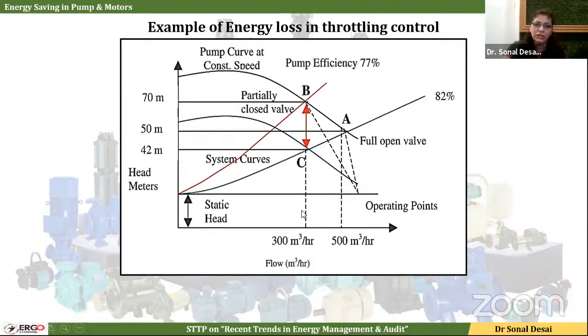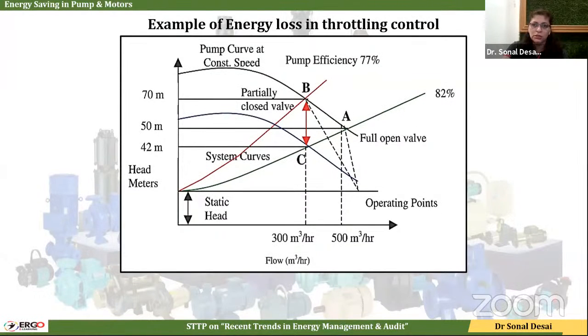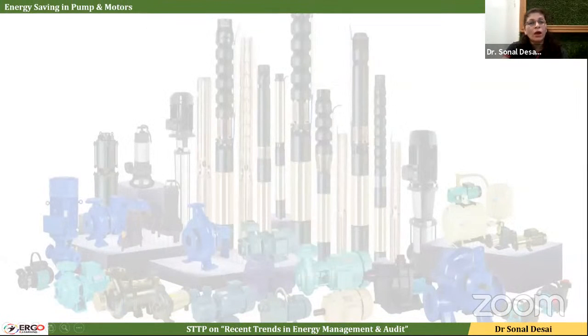So if 42 meter is okay with the application, I can have this achieved by trimming the impeller or reducing the speed. But again, it should be okay to match this gap, or else it is advisable that forget pump A, go for the new pump. That is even cheaper to run the pump in the long run. We will see the case study for this to understand this.